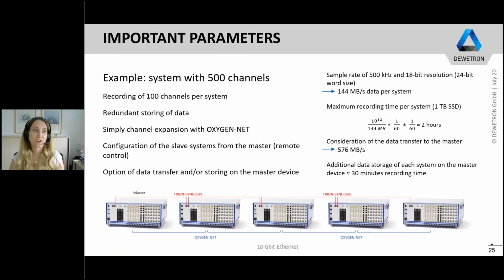So if we have a system with 500 channels and record 100 channels per system, I constructed the system here with our Oxygen Net option, where you can connect all these systems very easily. They are synchronized by the Trion-Sync bus, and with the Oxygen Net option, we also have the option of data transfer and storing on the master device. The configuration of all the slave systems can also be done from the master device. Speaking of remote control, you can just sit in front of the master device after setting up everything and then configure each system individually.